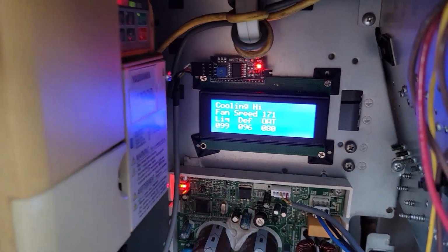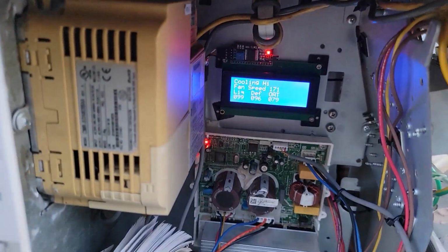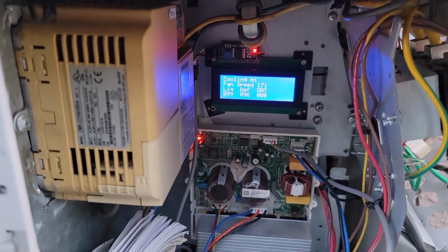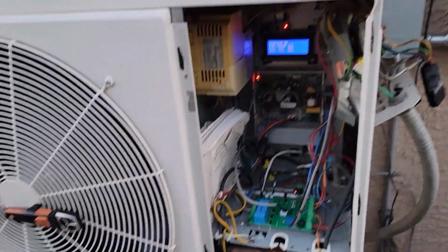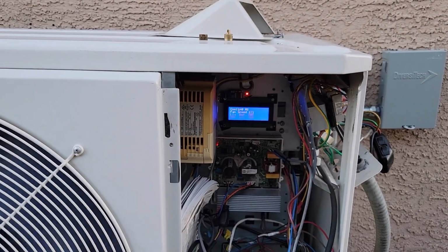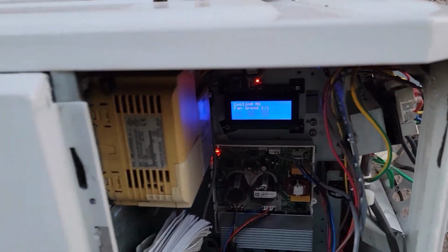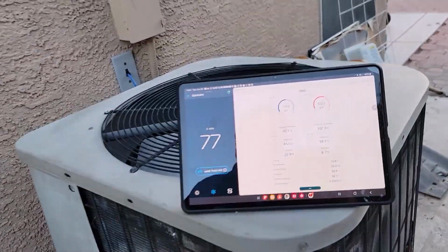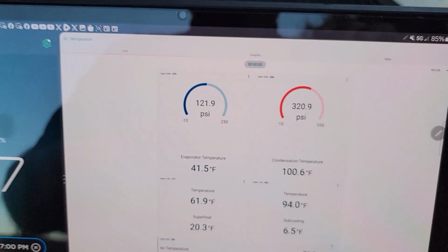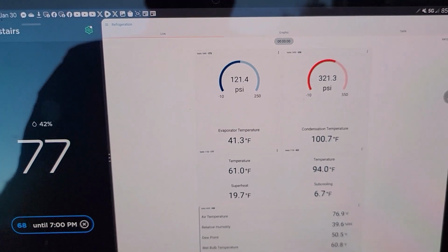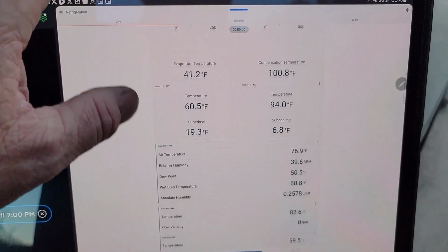Fan speed's still kind of maxed out. Liquid line's 99. And what I did yesterday was I kind of manually got in there and limited the fan speed a little bit just to drive up the pressures. Last night anyway. Got about a 3-to-1 compression ratio. Usually want to have at least that, so we're close.